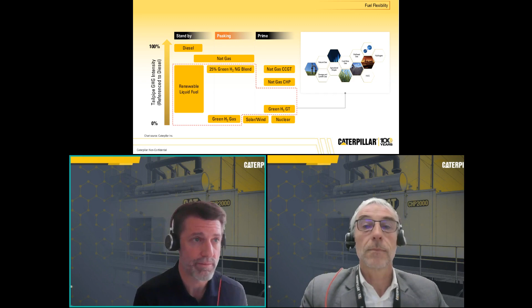Amongst the vast variety of customers' applications we serve, there are three main operational modes. You will recognize here the two standard ratings defined by ISO that you may know, which are standby, to make it very simple, equipment that ideally never runs. The genset would really be there as backup only, to cover any grid or intermediate electrical system issue.